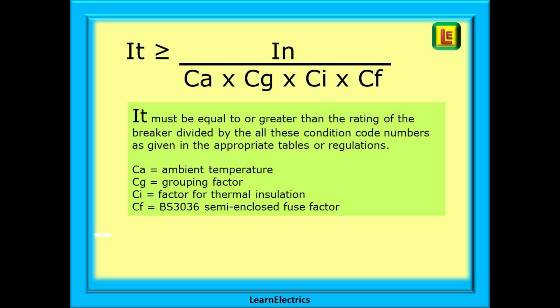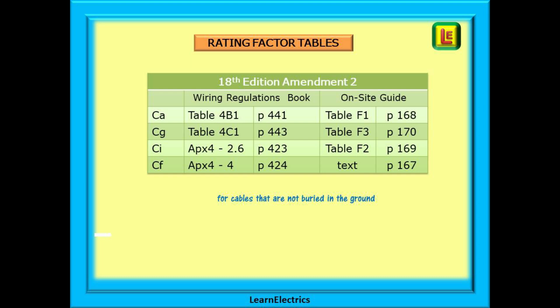This tells us that IT must be equal to, or greater than, the rating of the breaker divided by all these condition code numbers as given in the appropriate tables or regulations. The more common of these are CA for ambient air temperature, CG for grouping factor, CI is the factor for thermal insulation, and CF is the BS3036 semi-enclosed fuse factor. The table shown here lists these four rating factors and tells you where to find the relevant tables in the wiring regulations book and in the on-site guide. These tables are for cables that are not buried in the ground.